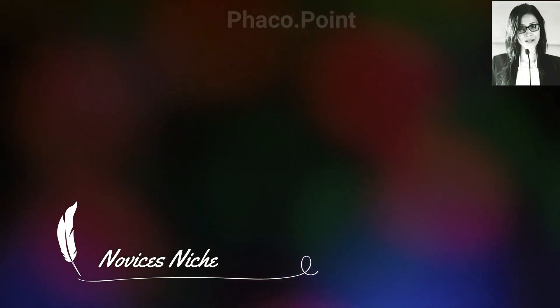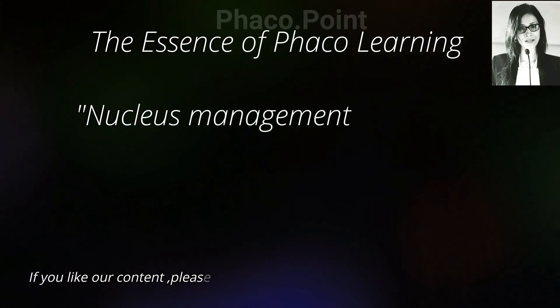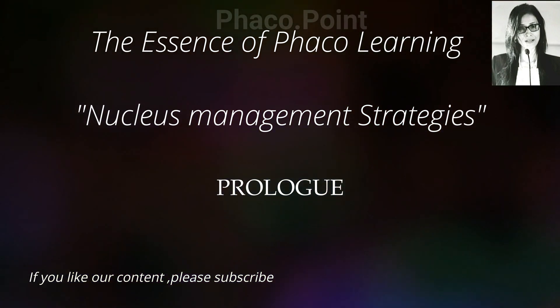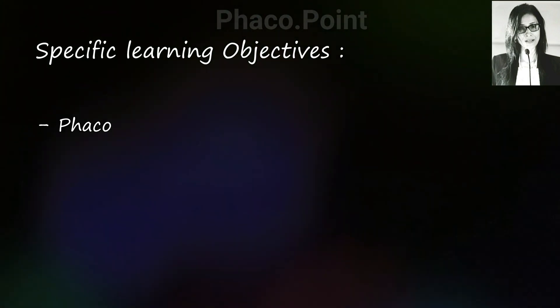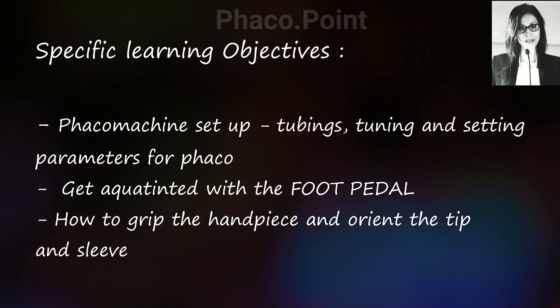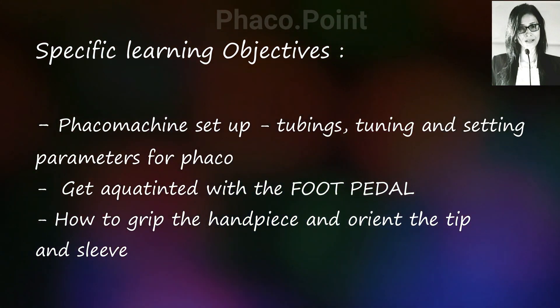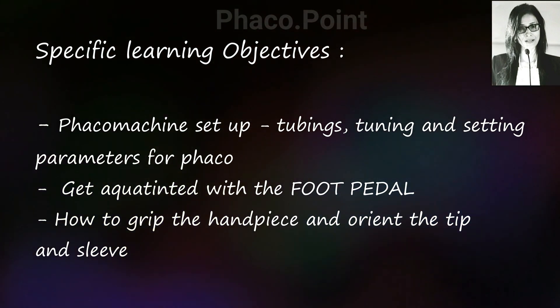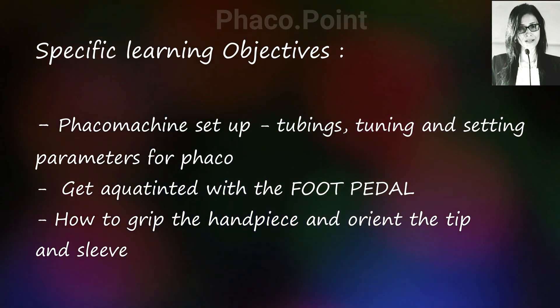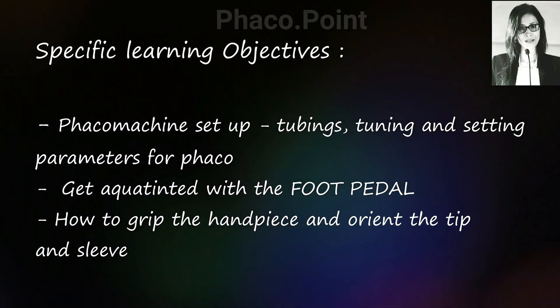This video helps you get started with phacoemulsification. At the outset it's very important that we understand how to set up the machine, understand what are the power, vacuum and flow settings in your particular console. It's important that you have the engineer at hand for your first few cases, who will help you fine tune the machine setup and the best power modulation, flow and vacuum settings based on the technique you choose for different grades of cataract density. Once you've understood the machine setup and the console, we move to understanding the foot pedal.